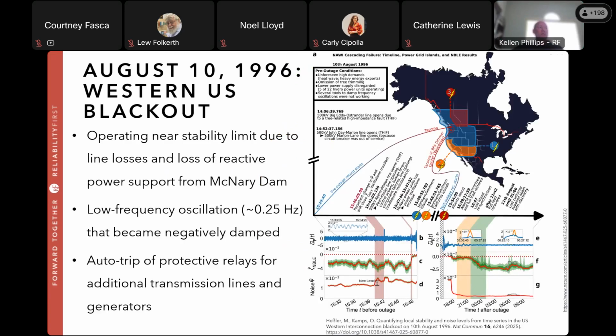This example is from August 10, 1996, known as the Western U.S. Blackout. As we know from Slido, this was a natural oscillation, specifically about 0.25 hertz, which became negatively damped. Its amplitude grew and grew rather than fading after each disturbance. The 1996 event reinforced the importance of monitoring grid dynamics and led to the development and widespread deployment of advanced sensor technology, such as synchrophasors and mode meter software, to identify and mitigate unstable power swings before they cause widespread outages.